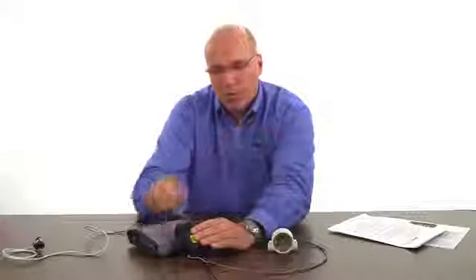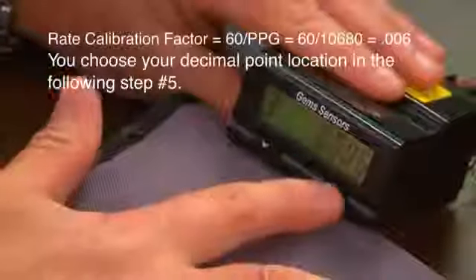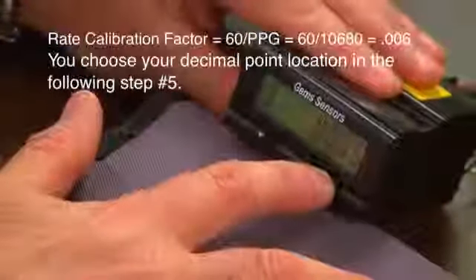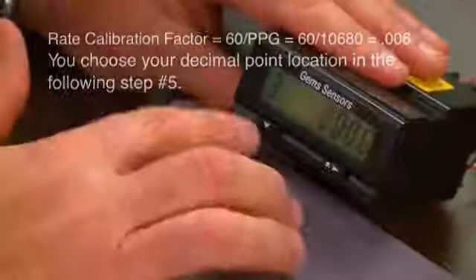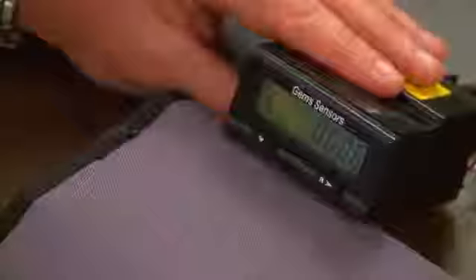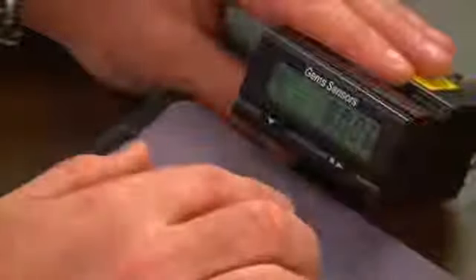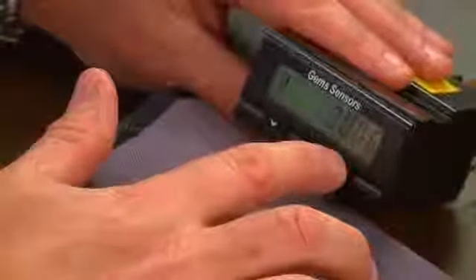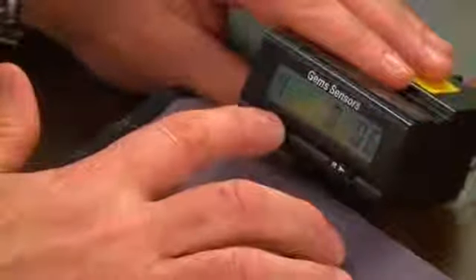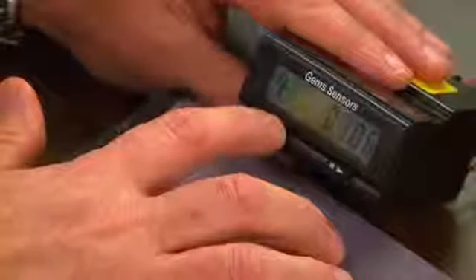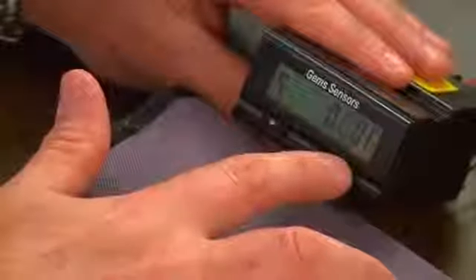Step 3 is setting the decimal point for the scaling factor we're going to put in for rate. Again, it's just a mathematical formula, knowing the number of pulses that come out of the meter that equal 1 gallon. See the little decimal point lining up? As I press the R button, it just lights up into a different spot. I want it all the way to the far left to enter my scaling factor. The scaling factor that I'm going to put in there is 0.006 for this sensor. How you actually put it in, again, is you just choose the digit that you want to change, use the other key to change it. Let me leave it where I have it, which is 0.006 for this meter. You're at the end, you press the down key, you go to step 5.